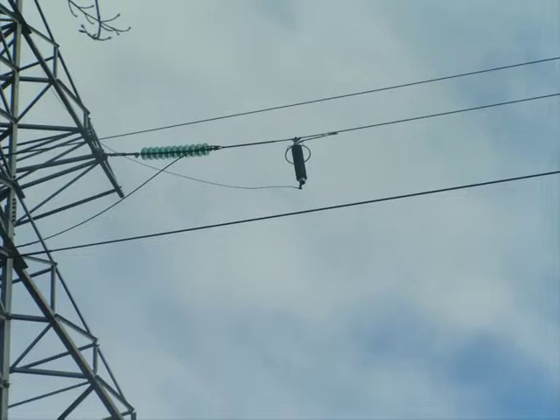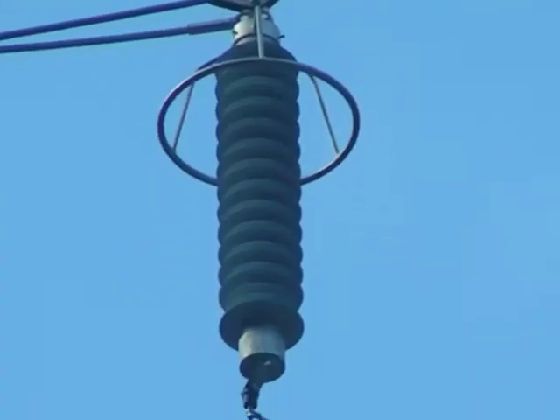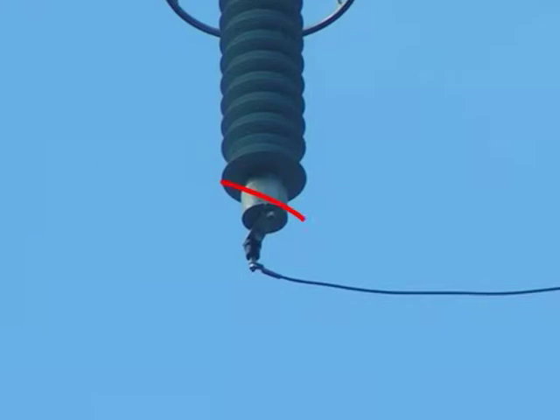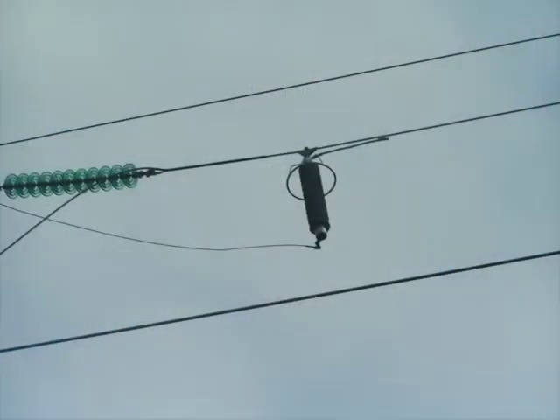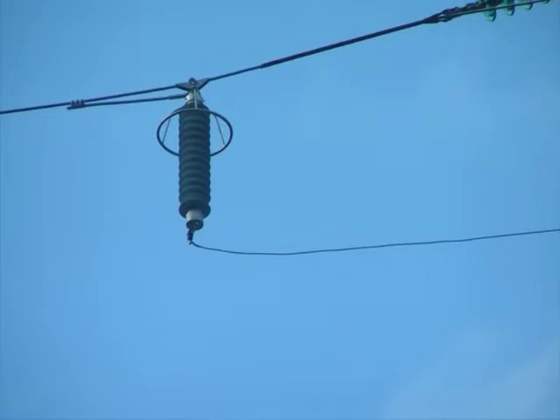In order to prevent a steady short circuit, a special device, a separator, is designed, which disconnects the looped circuit that connects the device with the tower or phase line, depending on the version of MOSA suspension. After the separator's response, the line becomes alive by automatic reclosure.